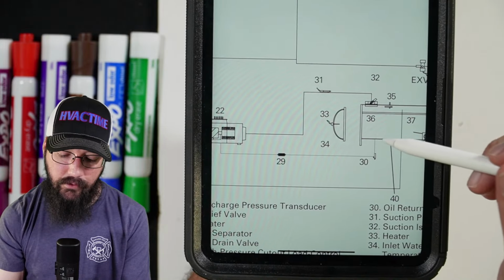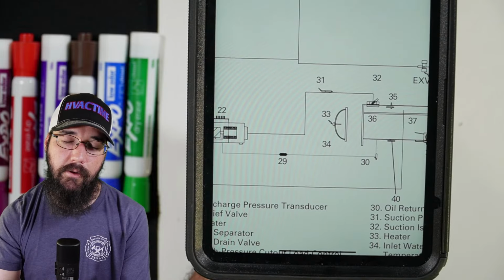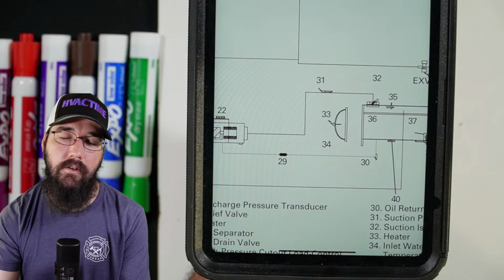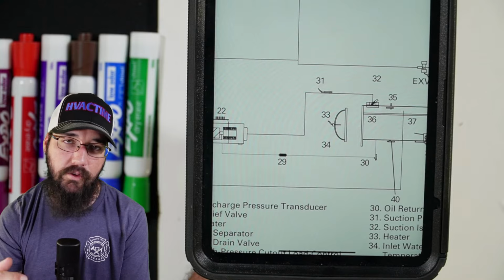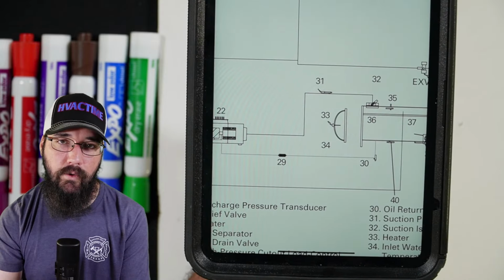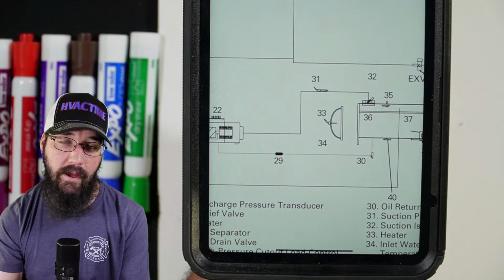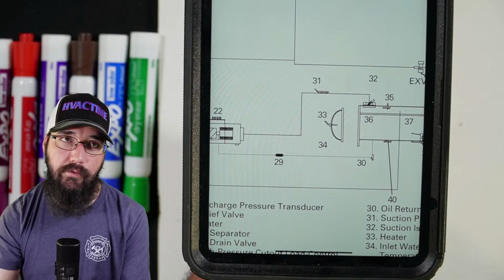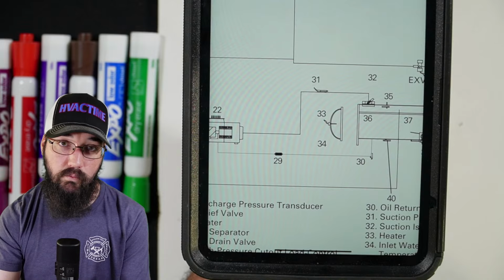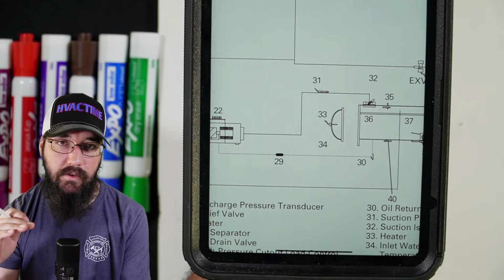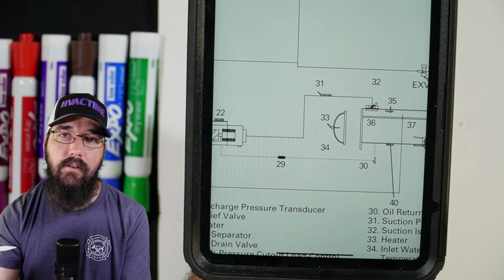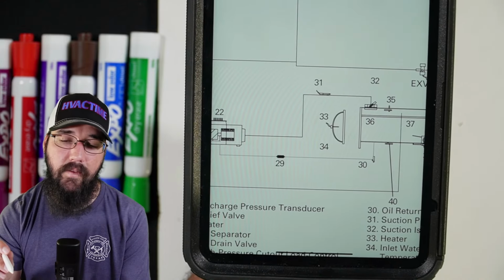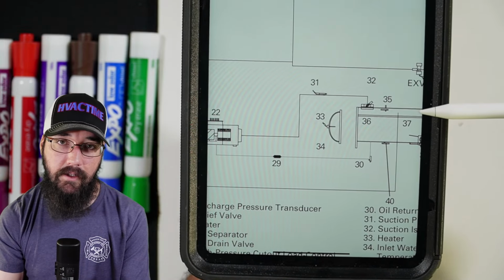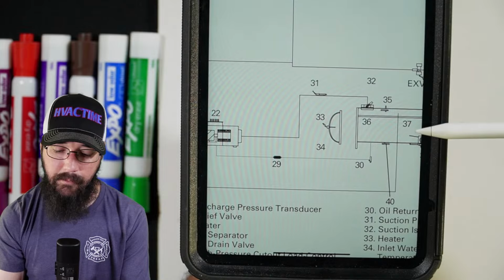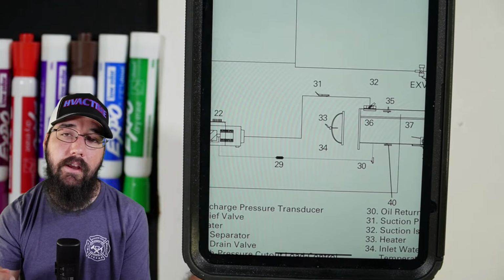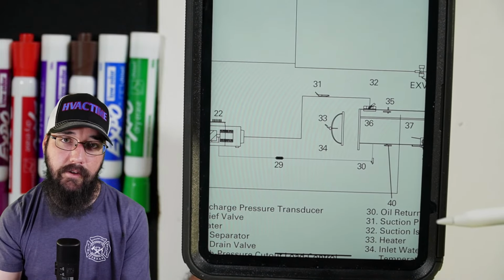Anyway, all of the liquid refrigerant in the bottom of the evaporator is mixed with a heavy oil to refrigerant mixture. Even though oil stacks on top of the refrigerant, it only perfectly separates when the refrigerant is not boiling off, when there's no flow happening. When there is refrigerant boiling because it is in operation, the top several inches of that liquid refrigerant will be an oil liquid refrigerant mixture. This is also true on larger machines that run higher liquid levels, up to half of the barrel could be liquid refrigerant. On those machines the top several inches are a mixture, even though oil floats.